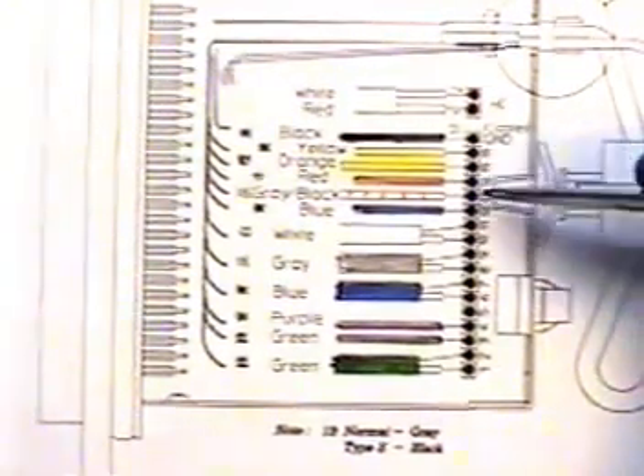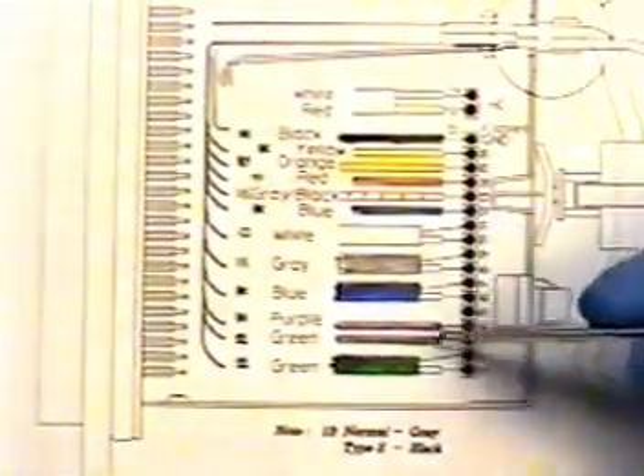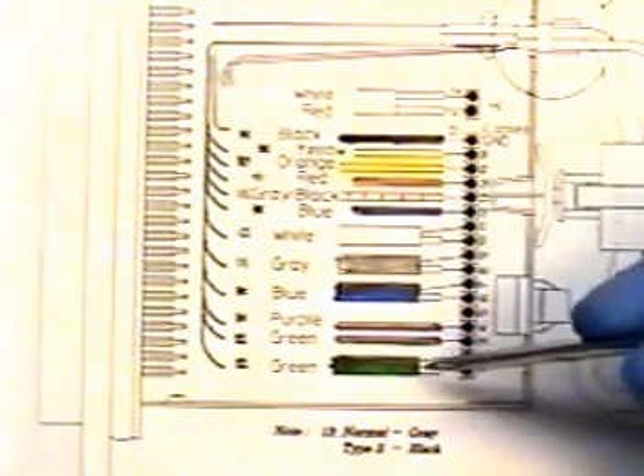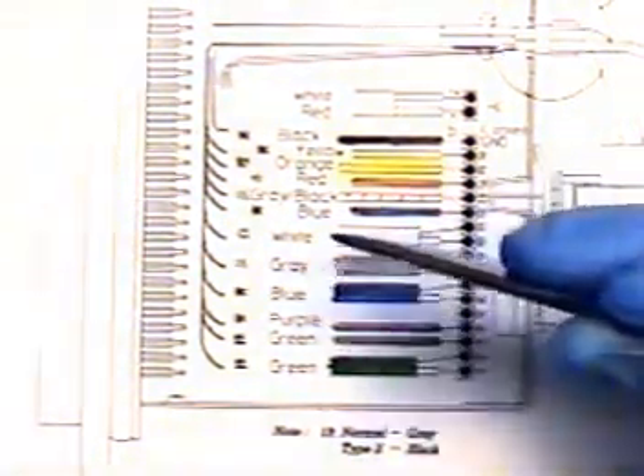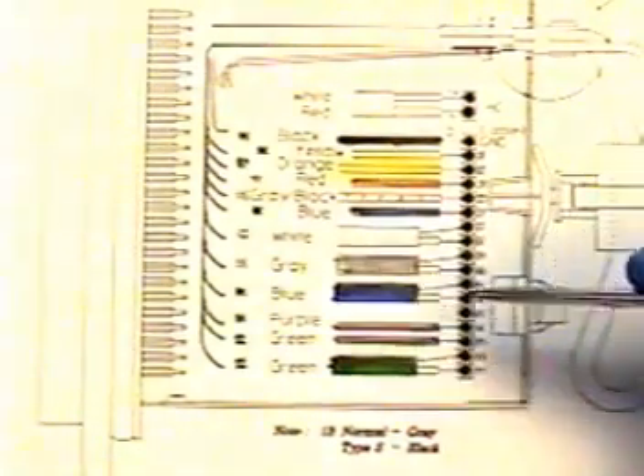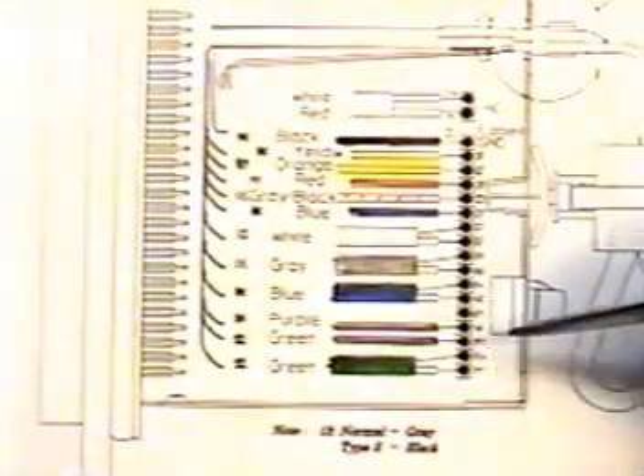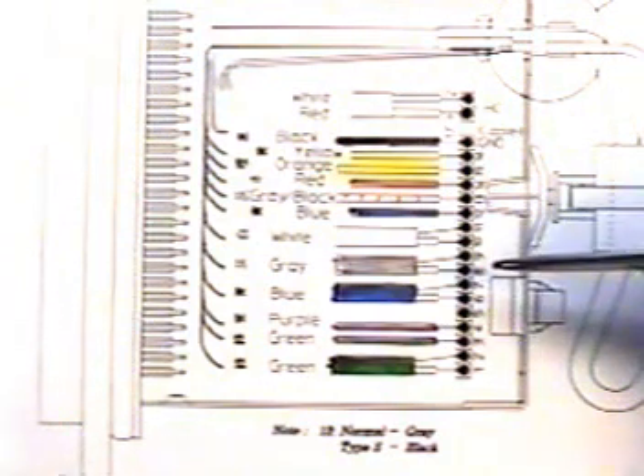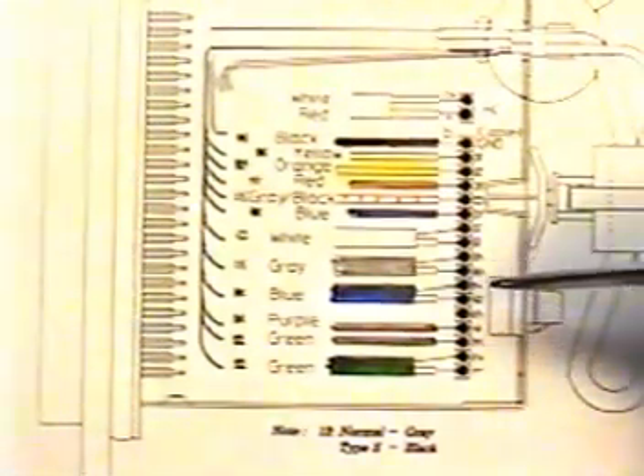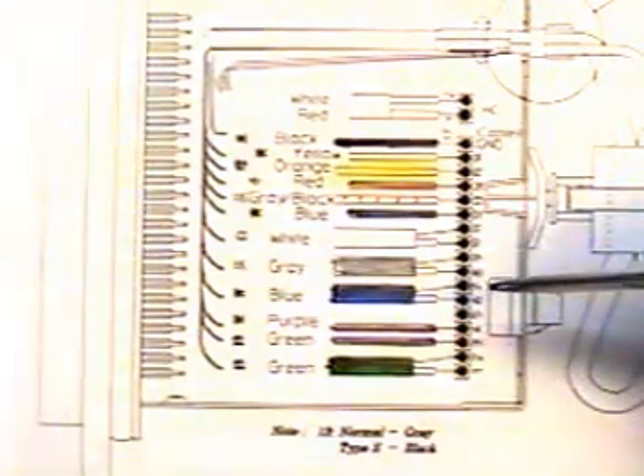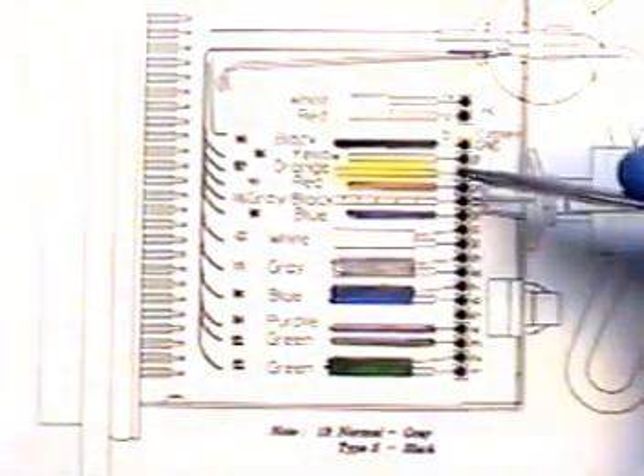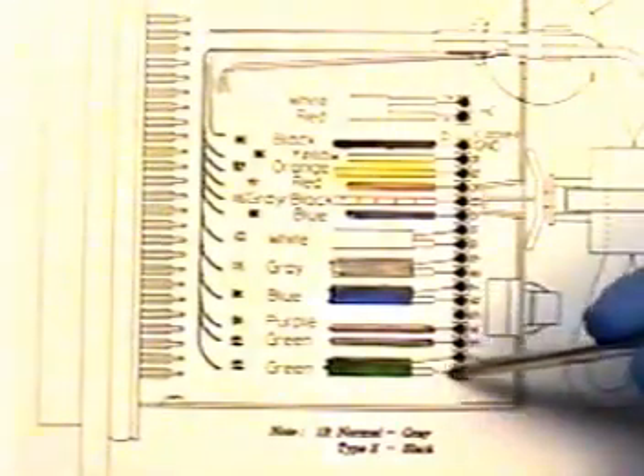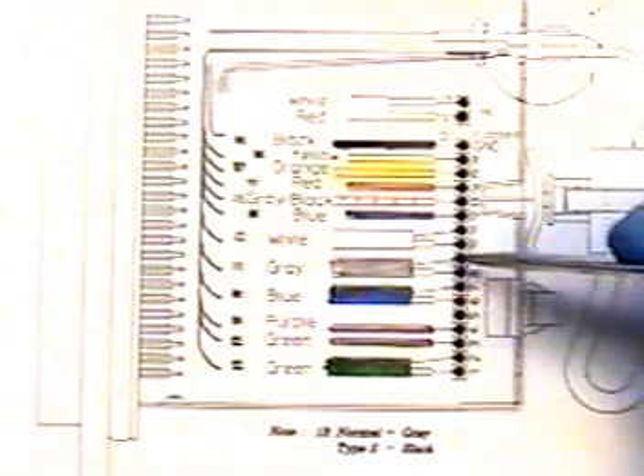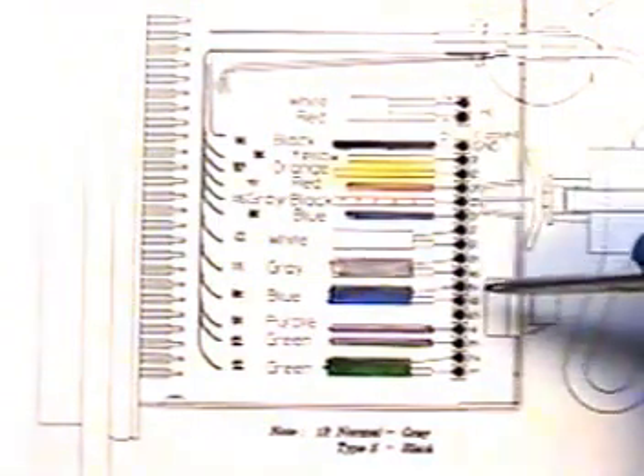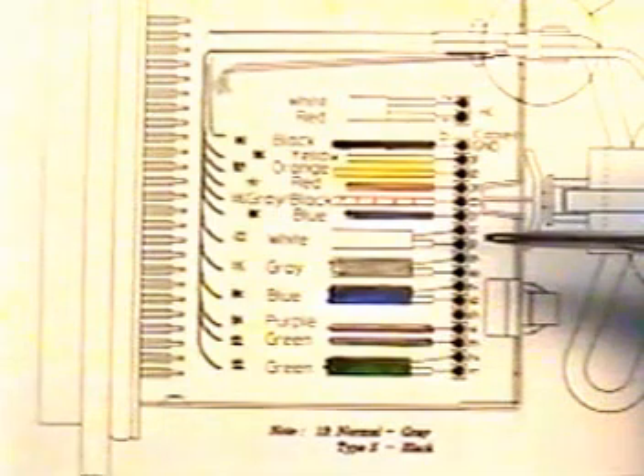Be sure you are statically grounded when soldering each and every one of these wires. Double check each wire after you have soldered them all on to make sure that they correspond to each color on this wiring diagram. After you have wired endoscope, plug into EPX 200 and test for video. If you still do not have proper video, you will need to cut each wire again and resolder each shield and lead into each respective point on PCB and retest in processor until you get video image.